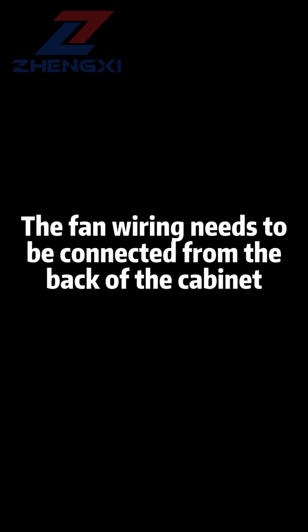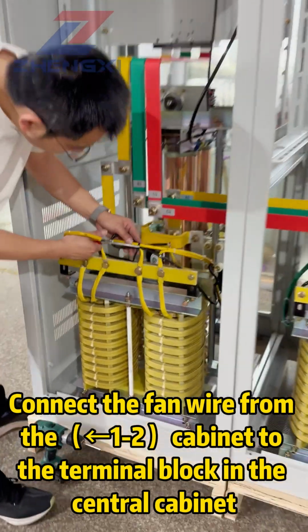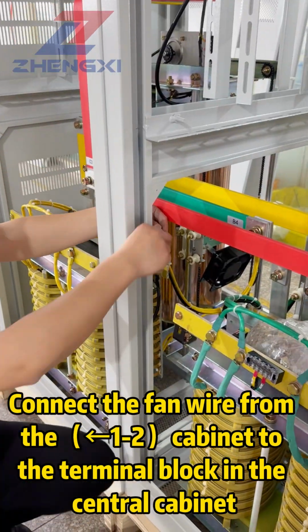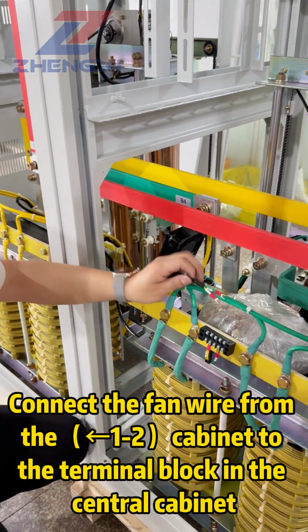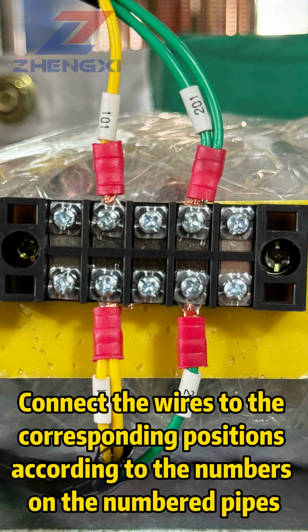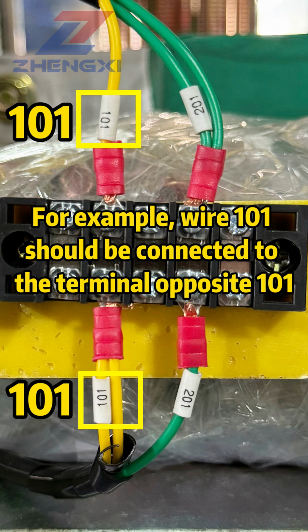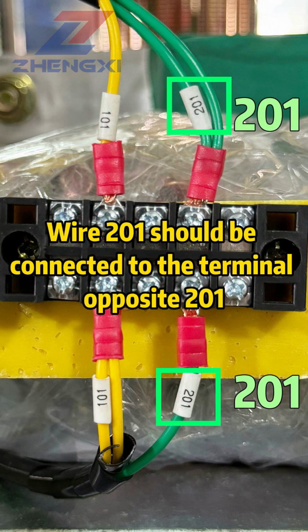Step 5. Fan wiring. The fan wiring needs to be connected from the back of the cabinet. Connect the fan wire from the 1 and 2 cabinet to the terminal block in the central cabinet. Connect the wires to the corresponding positions according to the numbers on the numbered pipes. For example, wire 101 should be connected to the terminal opposite 101. Wire 201 should be connected to the terminal opposite 201.